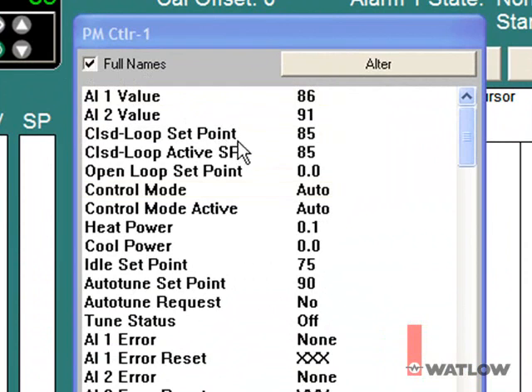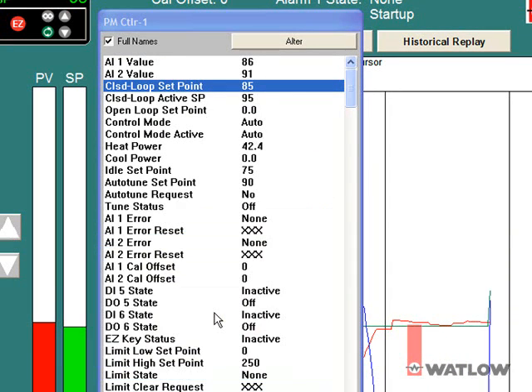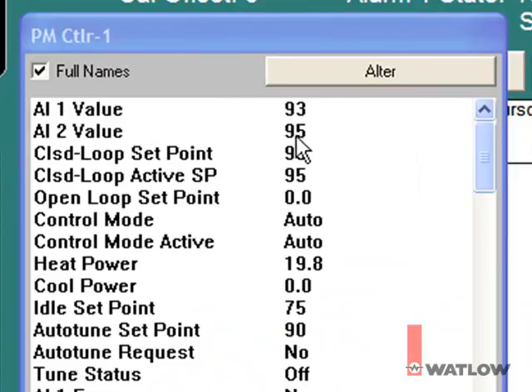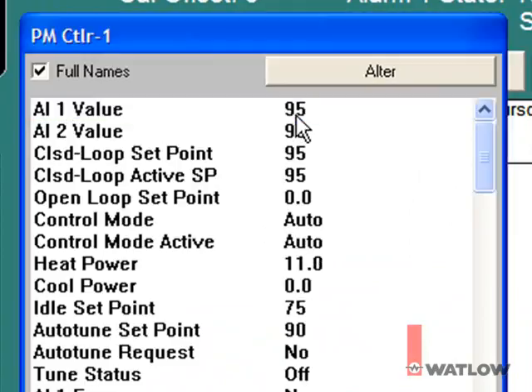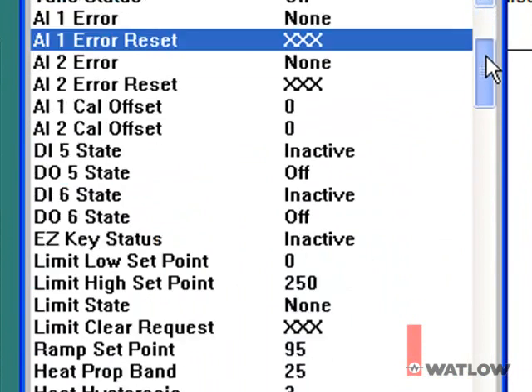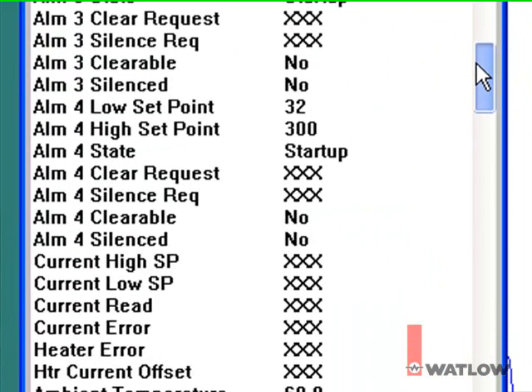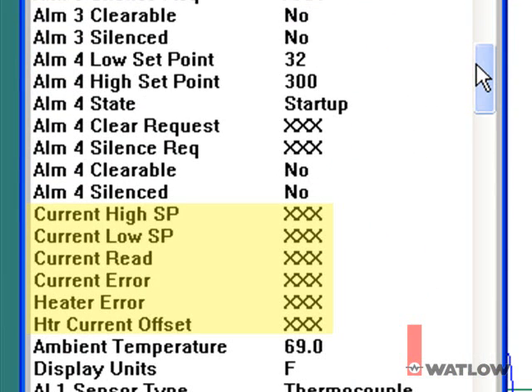Double-click a parameter to change its value. If you double-click a parameter and the keypad dialog doesn't open, the parameter is probably read-only and cannot be edited. Write-only parameters such as analog input error reset are displayed as three X's because while they can be written to, no value is read back. Other parameters displayed as three X's may be for features not included in your controller.